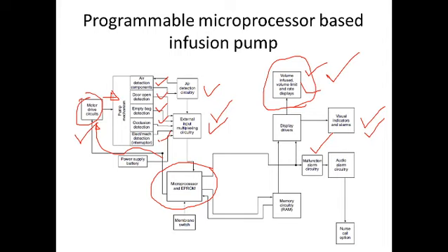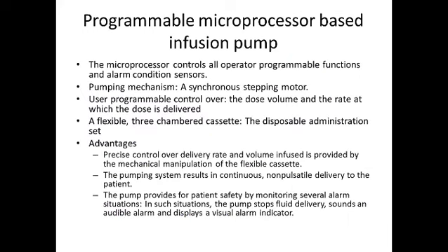You can generate an audio alarm, and you can also have nurse call options. You can initiate a call, an internal PBX call, so that the nurse will approach that particular area of the hospital. So this is the automated microprocessor based infusion pump, that is, the automatic drug delivery system.